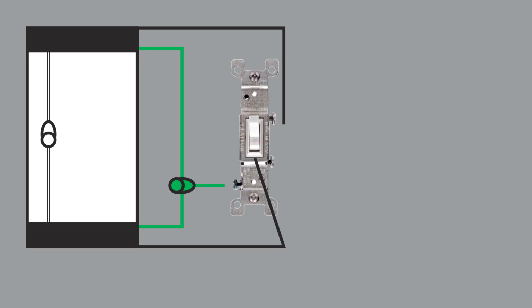If the bottom black wire supplying current to this switch ever came loose and came in contact with the body of the switch, you will receive a shock. This is why the green screw is screwed directly to the body of the switch. If the body of the switch ever became live with current, the current would travel through the green wire and back to the circuit breaker box. When current returns back to the circuit breaker box through the green wire, this will cause the circuit breaker supplying current to this device to turn off.